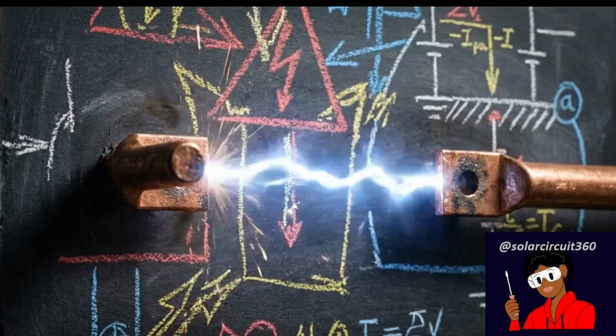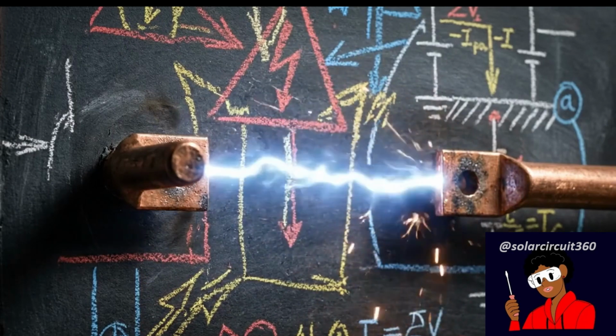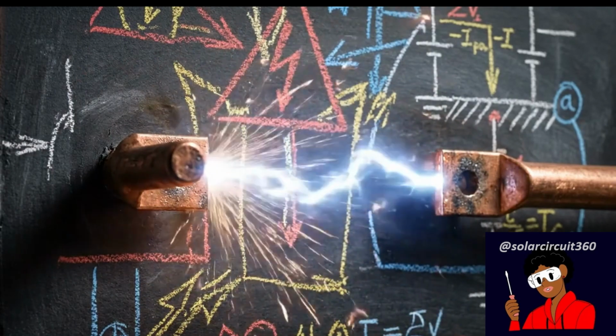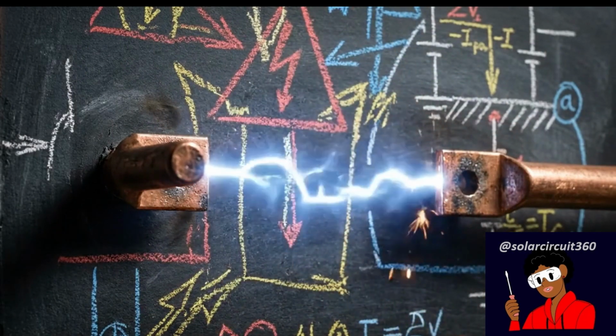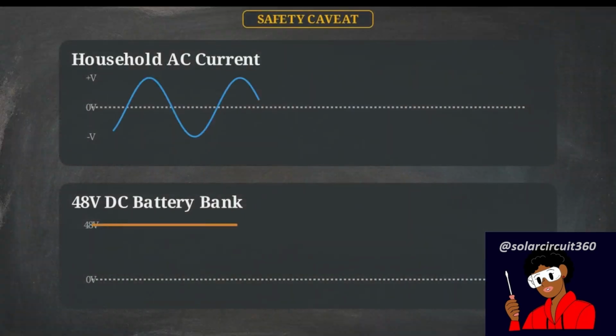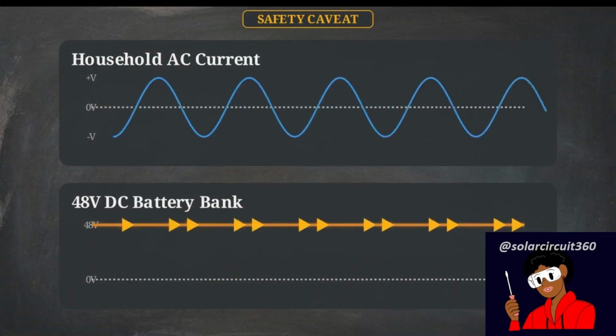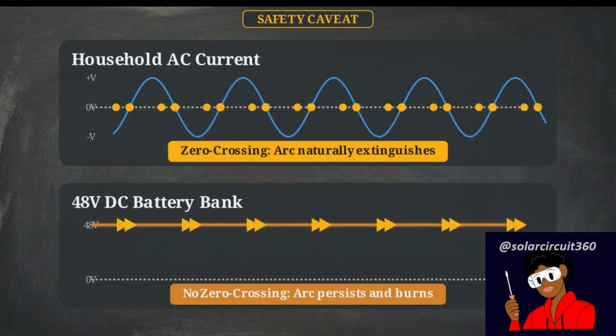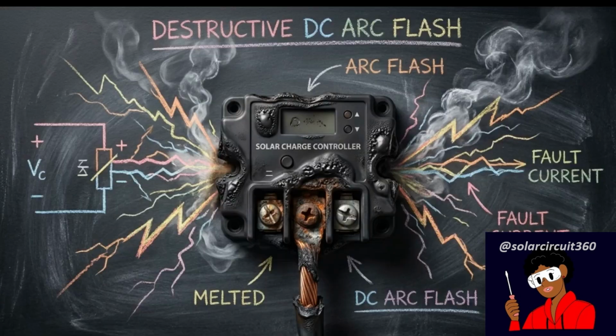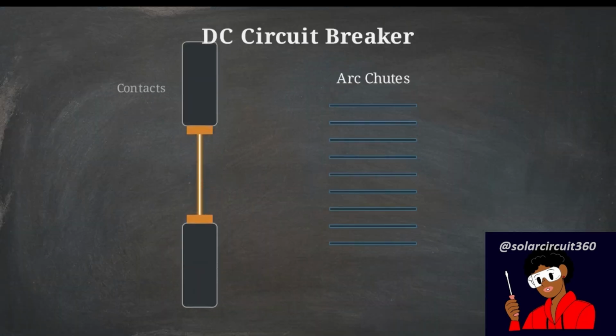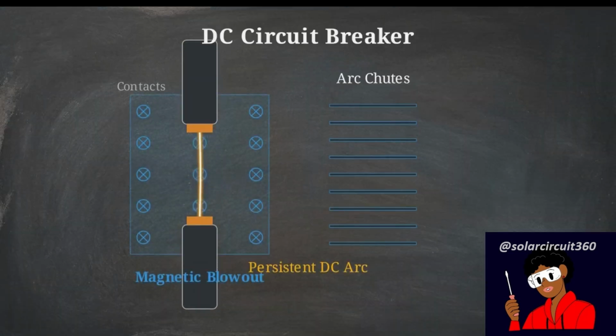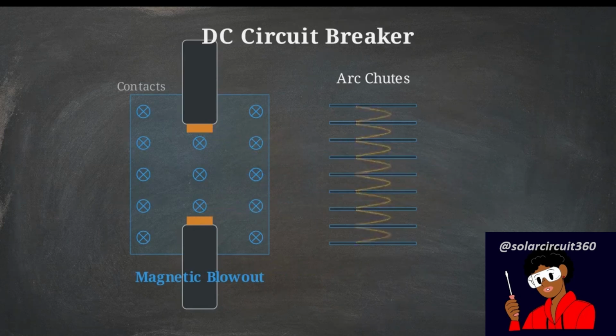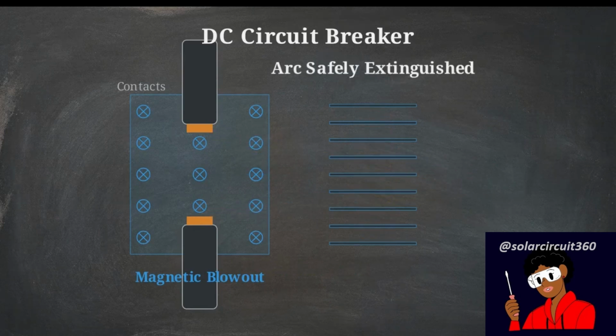Once unleashed across a physical gap, raw high-voltage direct current seeking the nearest ground cannot naturally extinguish itself. This introduces a strict safety caveat. Unlike household AC current that alternates and drops to zero dozens of times a second, a 48-volt DC fault will sustain a continuous, highly destructive arc flash. That behavior makes utilizing specifically rated DC circuit breakers, designed with internal magnetic blowouts to break arcs, an absolute necessity. Standard AC breakers will fail violently here.